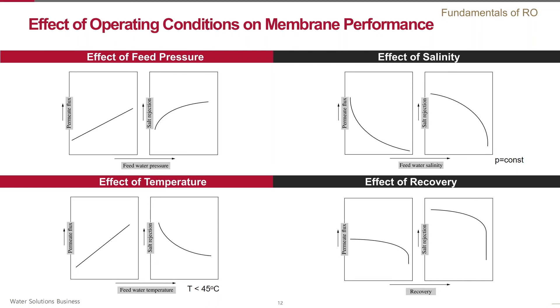The next figure shows the effect of salinity on flux and rejection under conditions of constant pressure. Salinity affects both flux and rejection directly: as salinity increases, the driving force for water flux decreases because of the high osmotic pressure, while the solute flux increases because of the high concentration gradient. Therefore, the apparent system rejection goes down. Temperature effects work in the opposite direction for flux and rejection.